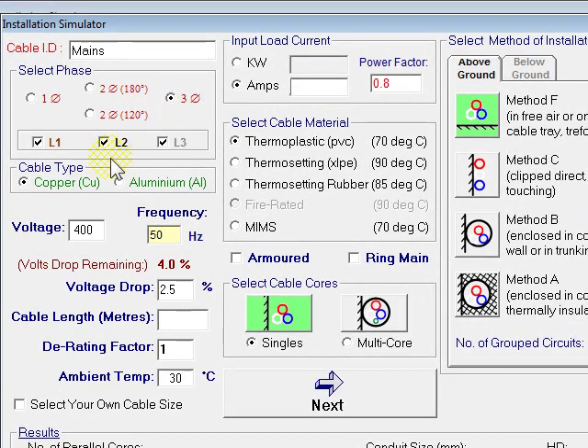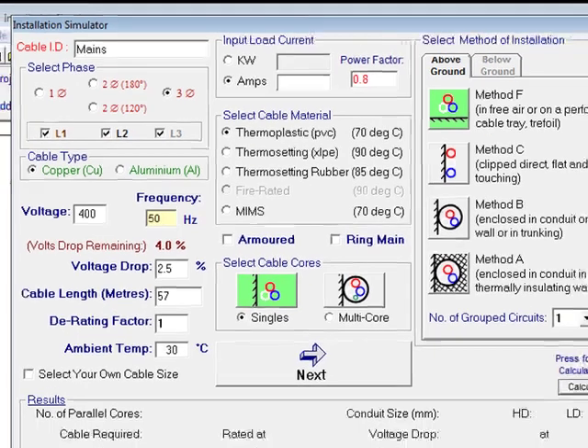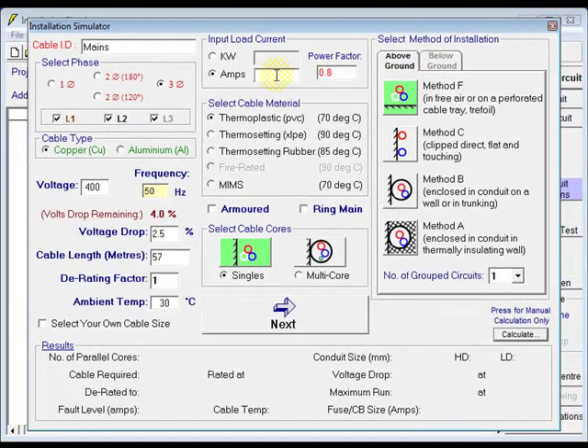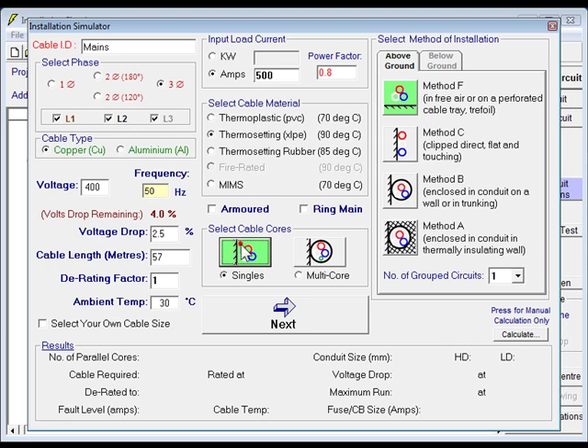It's three phase, copper, 400 volts. The length of that run, 57 meters. The current on that run, 500 amps. XLPE 90 degrees, in singles, and it'll be on a cable tray.